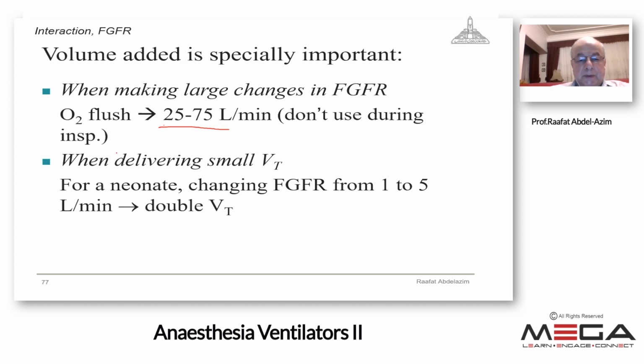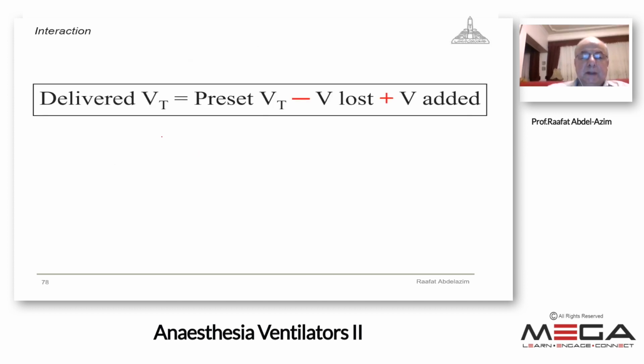The other important point is during delivery of small tidal volumes, like for neonates. Changing the fresh gas flow rate, for example from 1 liter to 5 liters per minute, will double the tidal volume, and this will lead to barotrauma. That's why we give pressure limited ventilation in neonates. Finally, the delivered tidal volume equals the preset tidal volume minus the volume lost due to circuit compliance plus the volume added due to the effect of fresh gas flow.